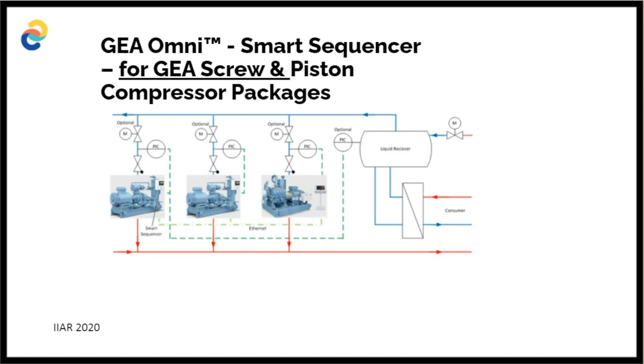Omni also incorporates this key driver, which is efficiency. So we developed a smart sequencer. And Dion also mentioned what type of compressor you're using. Well, sometimes it can be a combination, screw compressors and a piston compressor working on the same system. That piston compressor can be used for things like weekend duty. Very often when the store is not operating at weekend, then why run a big screw compressor set with a very large motor when you can do that duty with a much smaller machine?